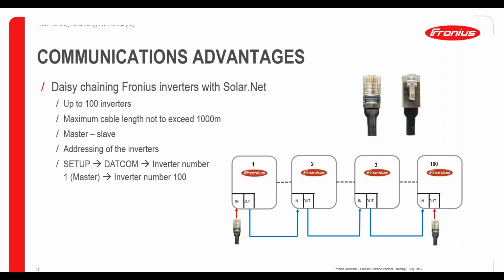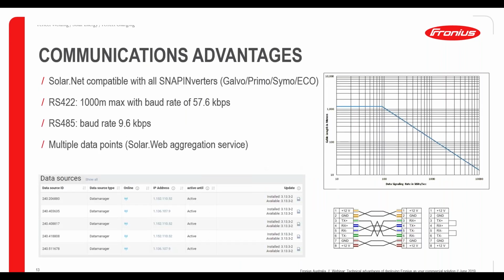If we go to the next slide, we'll go into a little more detail on what the SOLAR.net loop means. All these Fronius Snap inverters are compatible with this communication protocol, SOLAR.net. In the back end, two communication protocols are deployed. One is RS422, which is the communication between the inverters, and RS485, which is communication between any smart communication capable devices, such as Fronius smart meters, and the master inverter in this case. On the right here we have a typical graph which shows the maximum distance between typical communication protocols and the length of cable that can be used.